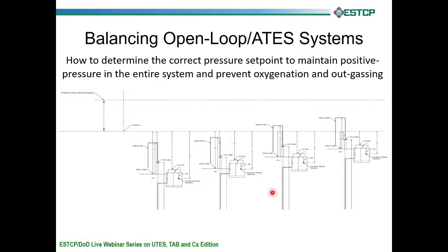So, like I said, we have two set points: maximum pressure and maximum flow. We have to figure out what we want our pressure set point to be. This is how we do that. This is a different job actually. There's only 4 wells instead of 6, but each one of these pits is at a different elevation because they're a long way away, and this job was not good and flat like Pensacola.